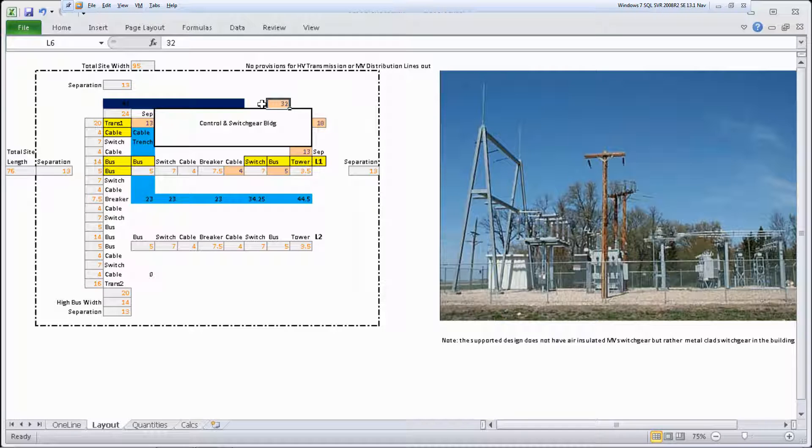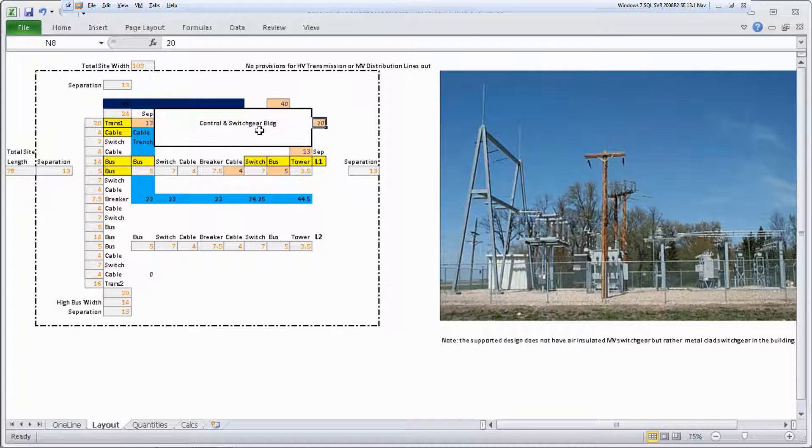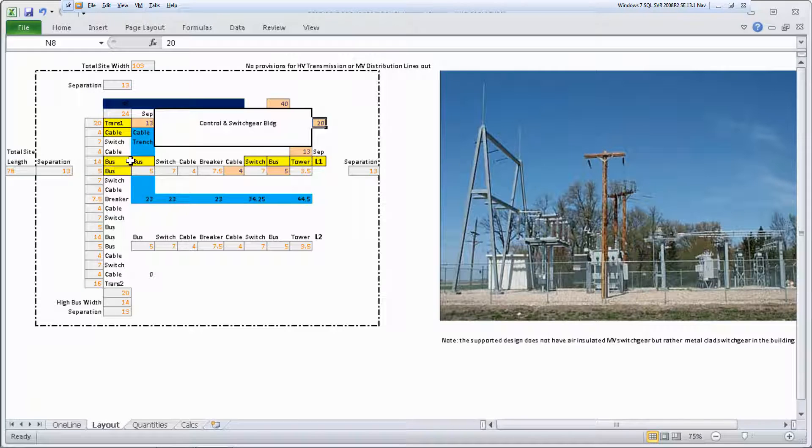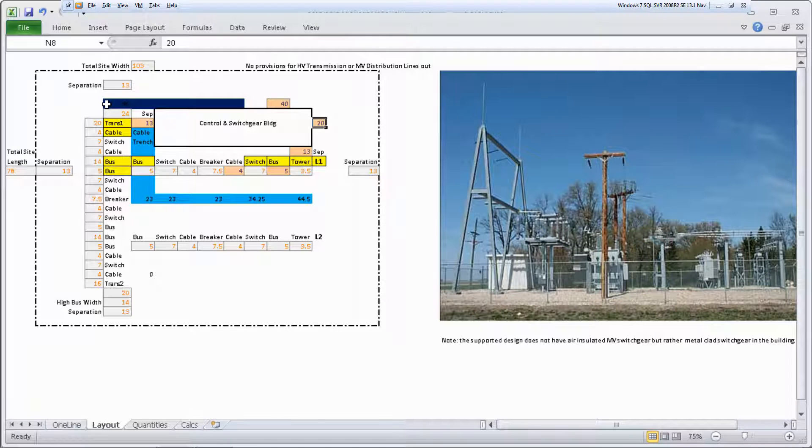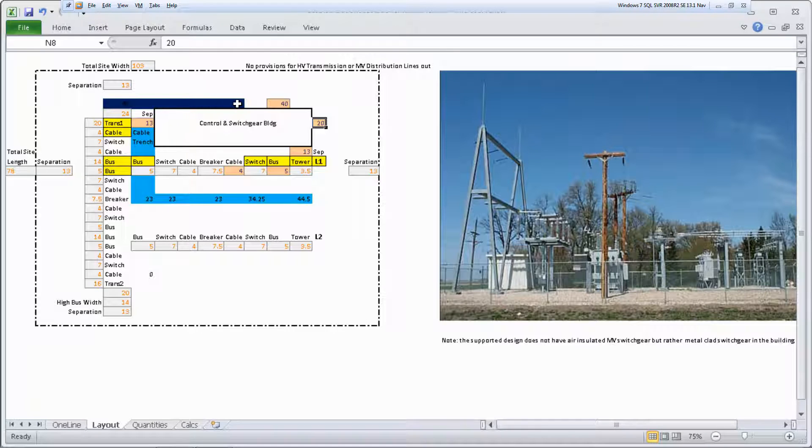Look over the default spacing and sizing values in the orange cells and change them as needed. Buses and equipment bays are highlighted in yellow, and cable trenches are highlighted in blue for easy identification. Dark blue indicates medium voltage cables going from the transformers to the switch gear. A photo of a representative substation is also included.